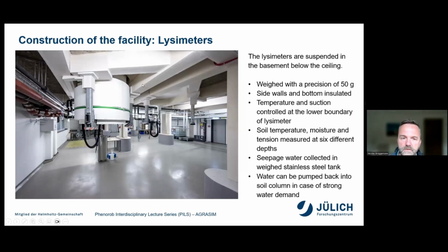The lysimeters are hanging in the basement. They are attached to the ceiling with a steel construction, hidden under this fire protection layer. And they sit on 3 feet, and each foot carries a weighing cell. So basically the weight of about 3 tons is weighed by 3 weighing cells. It's hard or impossible to see, but the whole weight rests on 3 spots of less than a square centimeter. That's the weighing cell. And the weights of the 3 cells are added and then give the total weight of the lysimeter.